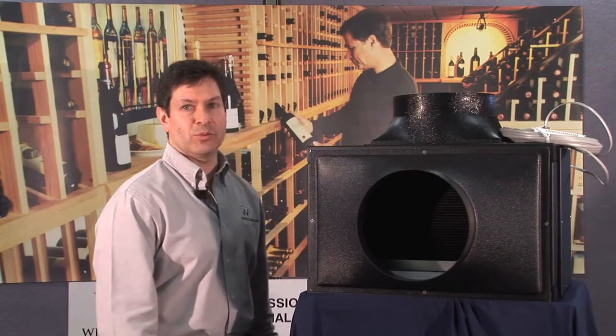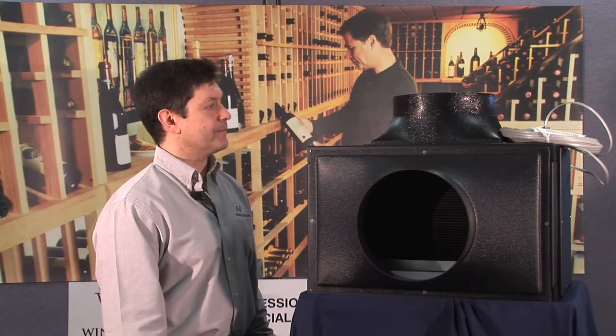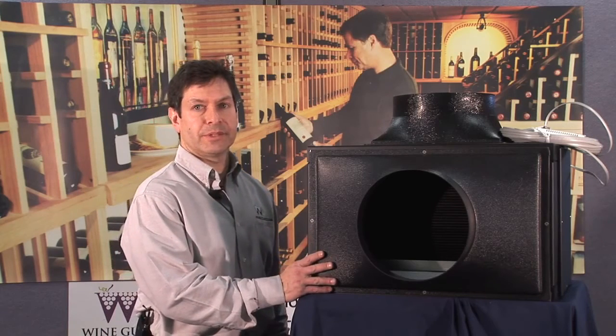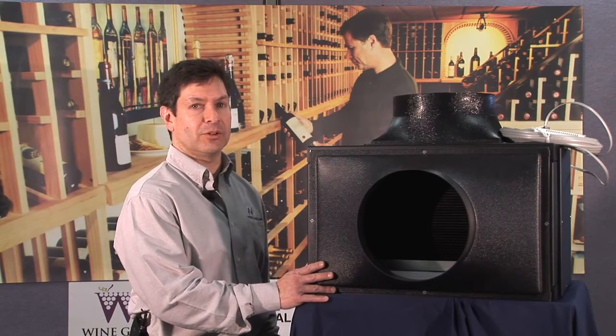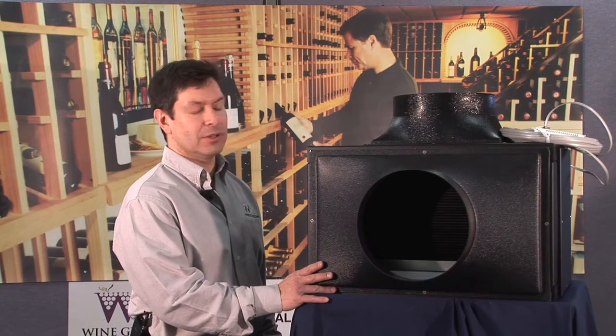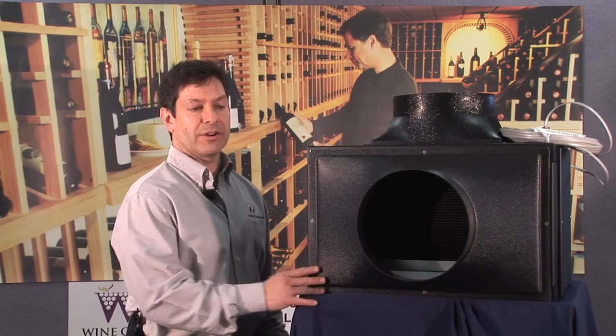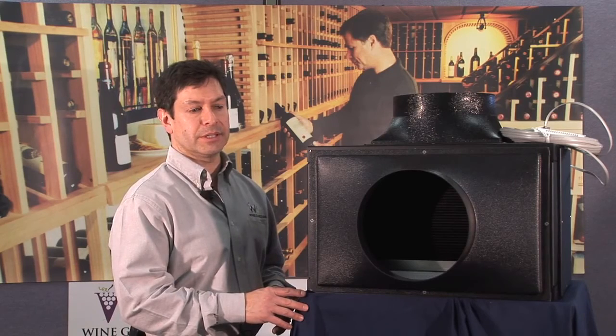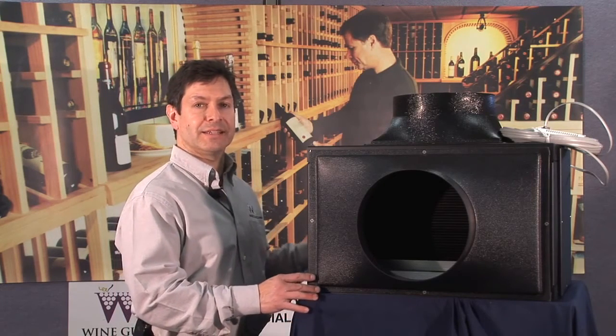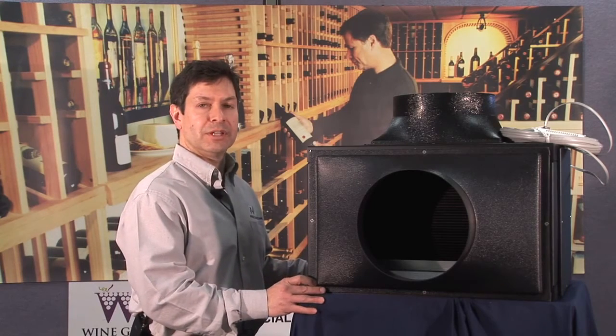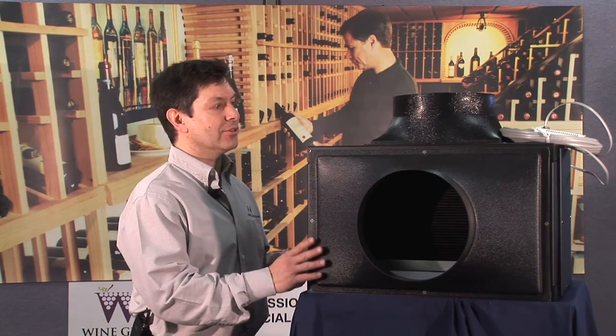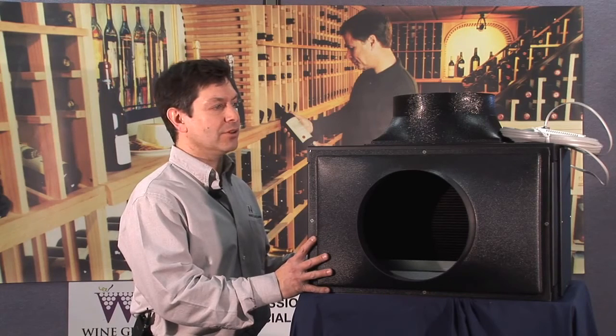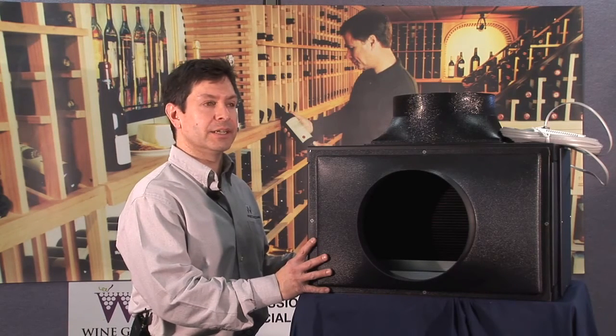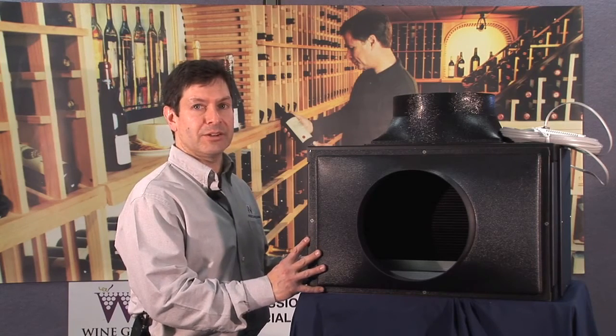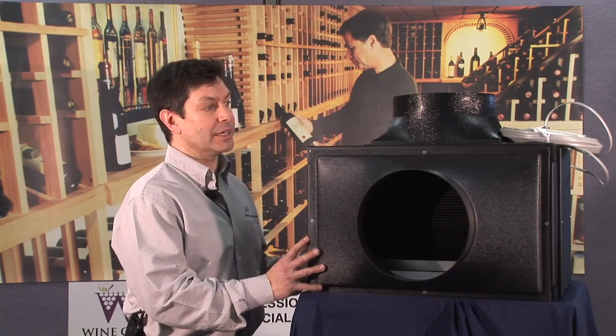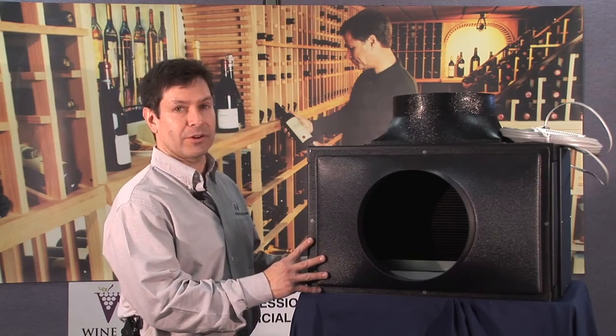Some of the options that are available with the split systems are an integral heater, ranging anywhere from a 1 kilowatt up to a 2 kilowatts of heat that can be added to the wine cellar. For areas where the wine cellar would require heat at some point in order to bring it back up to 55 degrees Fahrenheit, a heater is an option that can be installed into our fan coil sections at our factory. It should be noted that you will need to know that at time of order. But it certainly is an option that many of our competitors don't have.